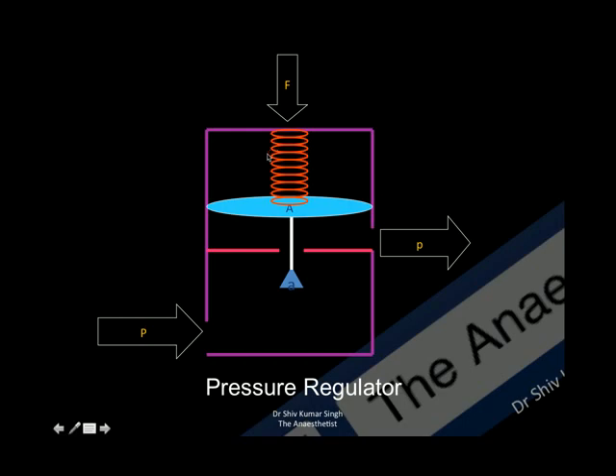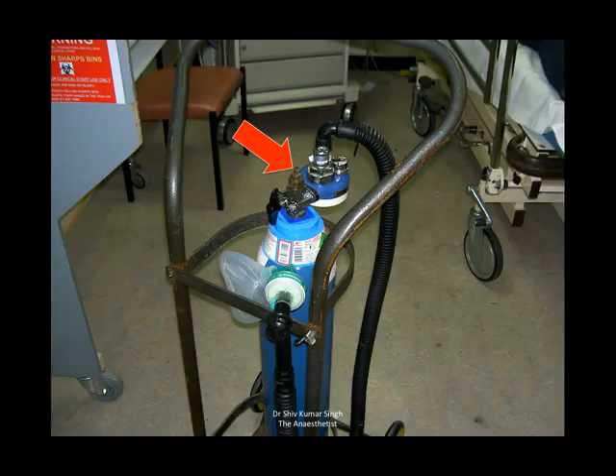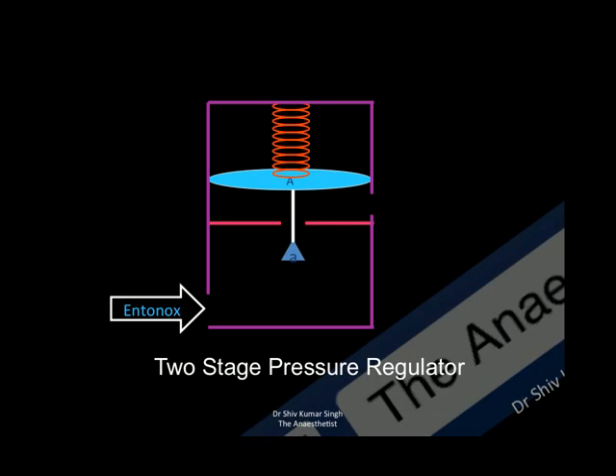The force is normally preset in pressure regulators depending on whether it is an oxygen or nitrous oxide pressure regulator. The Entonox valve is used for pain relief. The first part of the Entonox valve is just a pressure regulator as explained. It is called a two-stage pressure regulator, but the second part is not actually a pressure regulator — it is a demand valve.